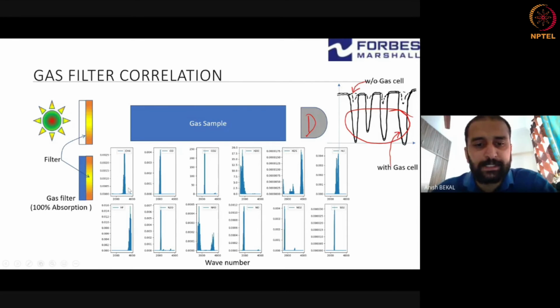If you look at the wave numbers, different gases have different characteristic wave numbers, and every gas can have multiple wave numbers. The advantage of this technique is that you can measure multiple gases in the same setup. With the same source, you can measure something like 6 to even 10 gases at the same time, whereas with UV, because of the limited spectral range you have access to, you can typically measure only about 4 at max. Here you can measure CO, CO2, water, and many others simultaneously. That's the good thing about this technique.